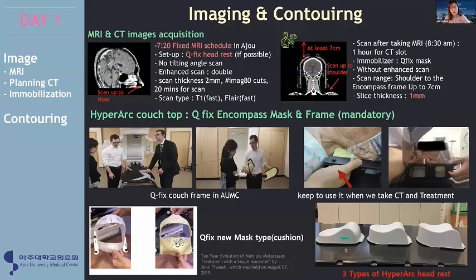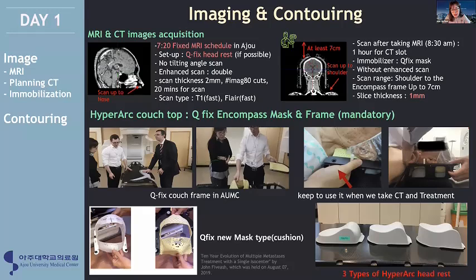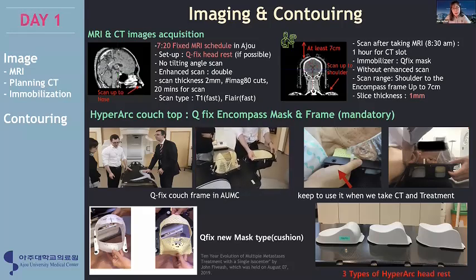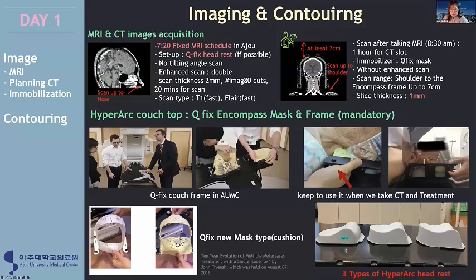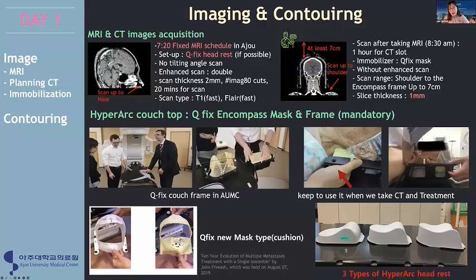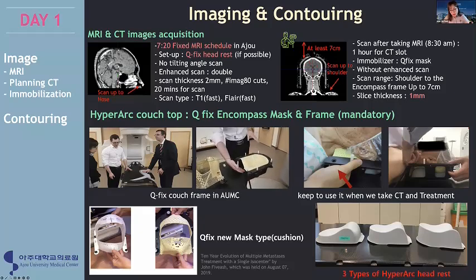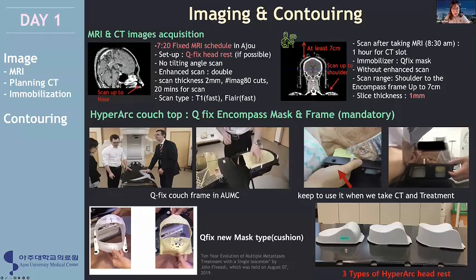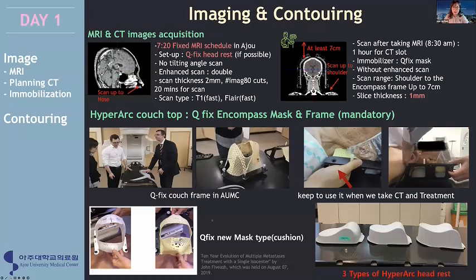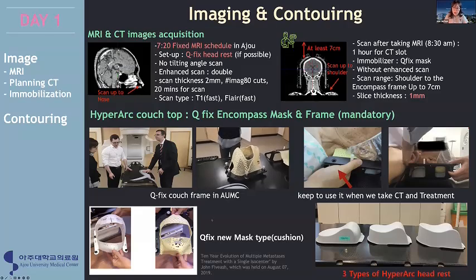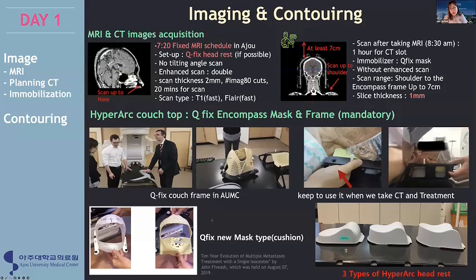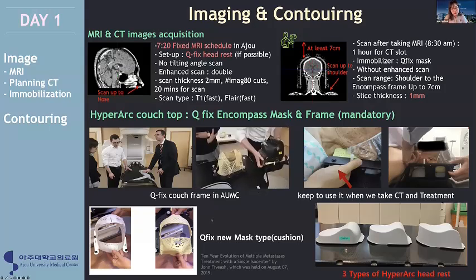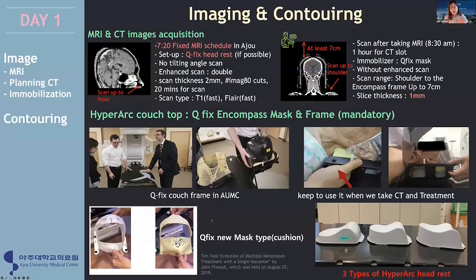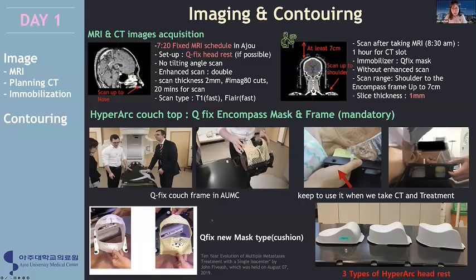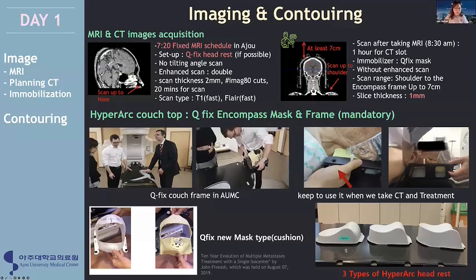We also get a CT scan with 1 mm slices, and the CT scan must include a minimum of 7 cm from the end of the frame up to the shoulder. It can be calculated by the system, and you can get more information about collisions in advance. We also use the QFix couch frame, which can be replaced like in this video, and we apply the QFix Encompass mask for the patients, which is mandatory for HyperArc. Additionally, we can selectively use 3 different types of headrest depending on the patient's posture.